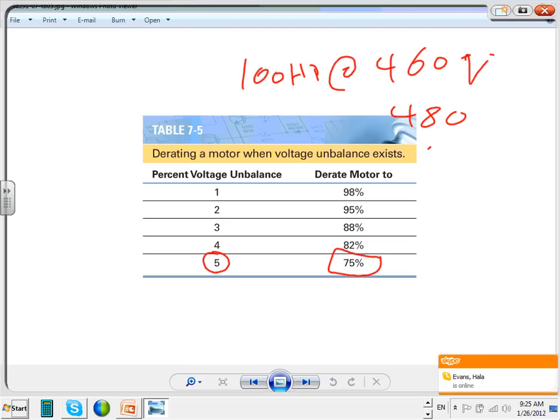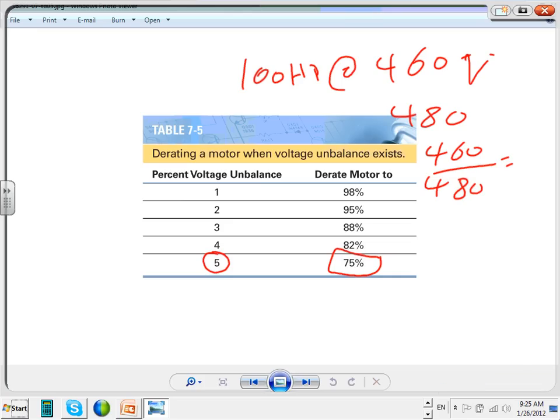So what's this one, Chris? 460 divided by 480. What's the percentage reduction? You have a calculator handy? 460 divided by 480. So look at this, that will give you 96%. I can reduce my voltage up to 96% of the nominal voltage, and my motor is still up and running.